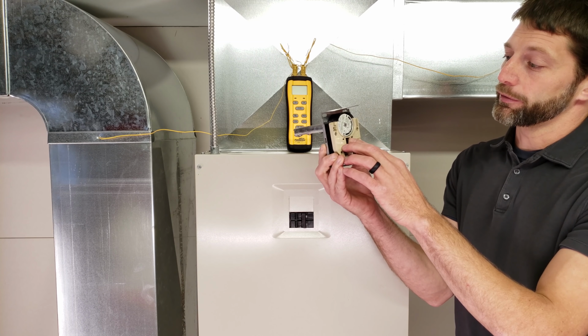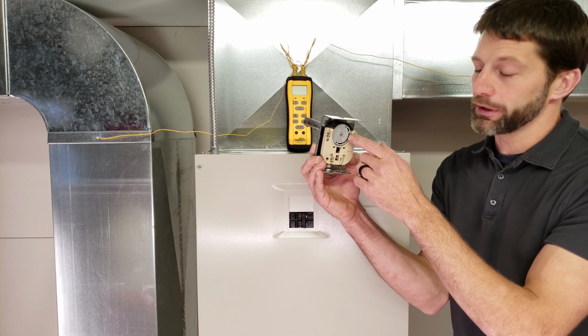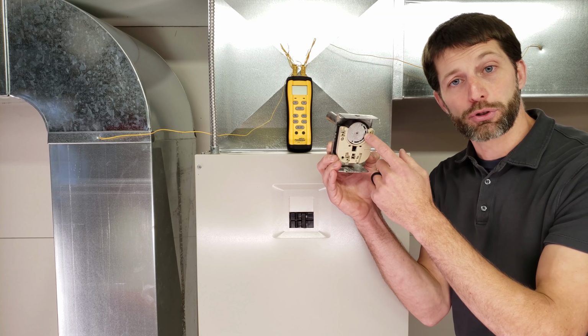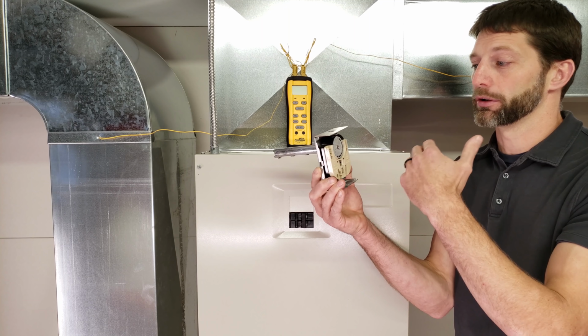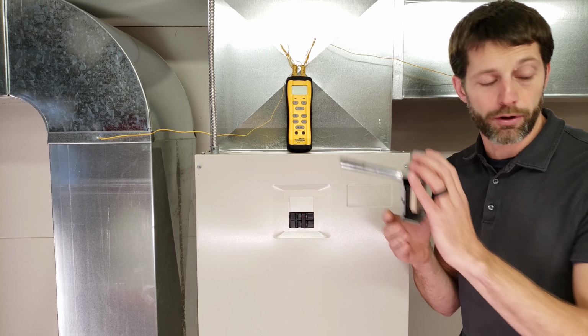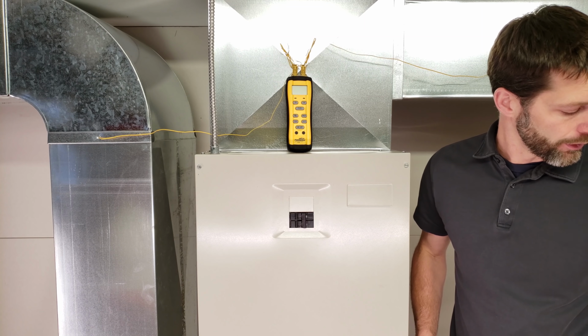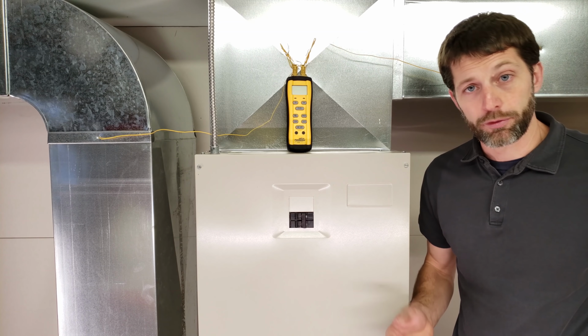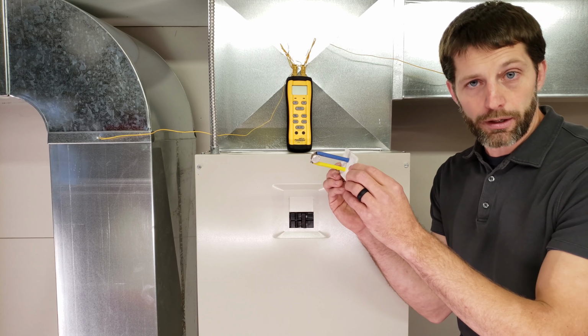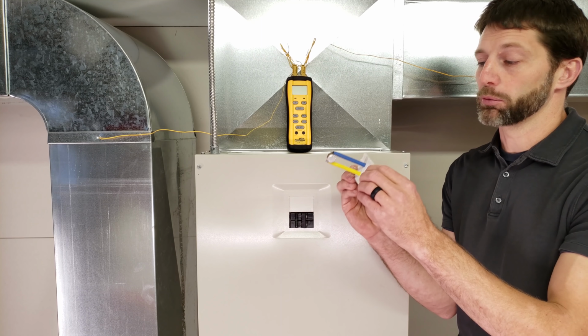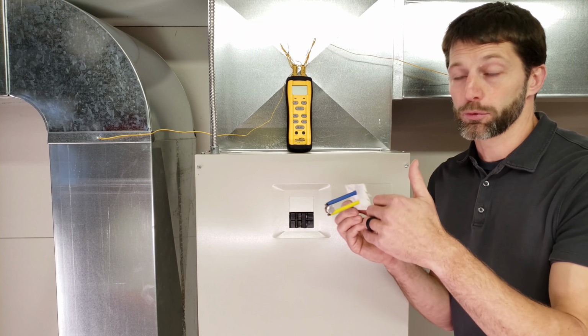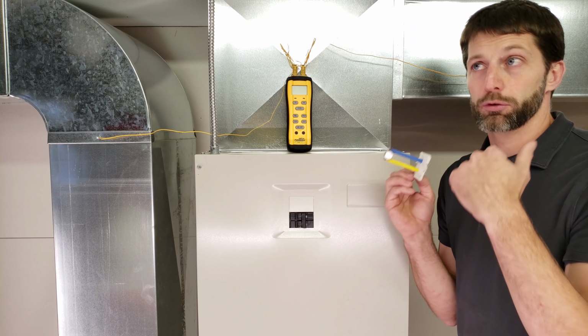So this is usually used on an oil-fired furnace or older gas furnace. And this is a fan limit switch, and you have your third knob right here. That's your high temperature limit. So this would shut your ignition off on a gas furnace. You also have on gas furnaces something that may look like this, and it's a temperature limit, and it's near the heat exchanger area, and this will open up if the heat becomes too high because you're not able to reject it into the building.